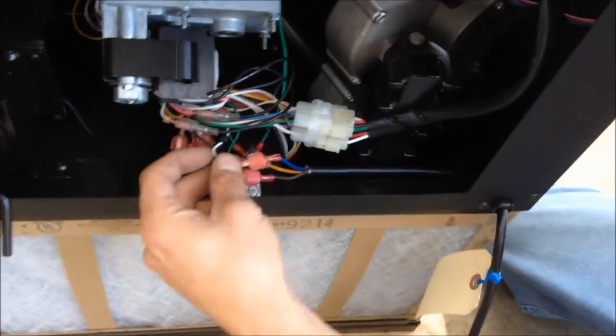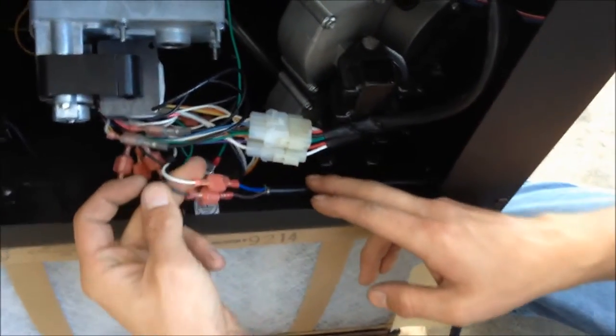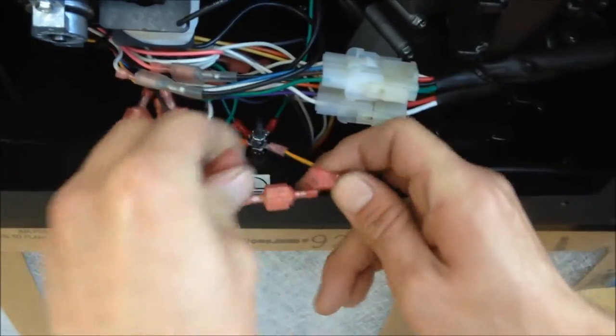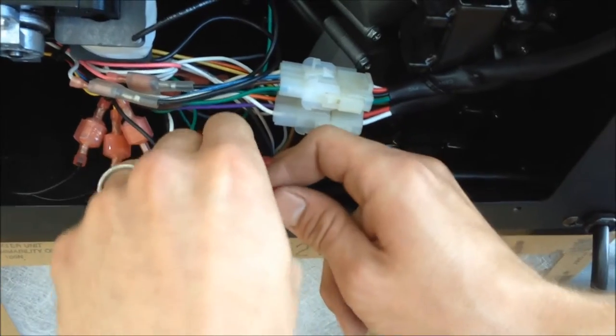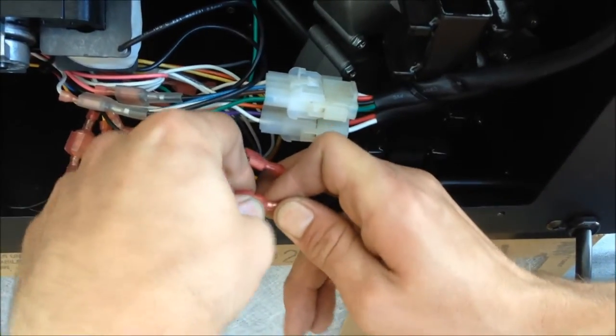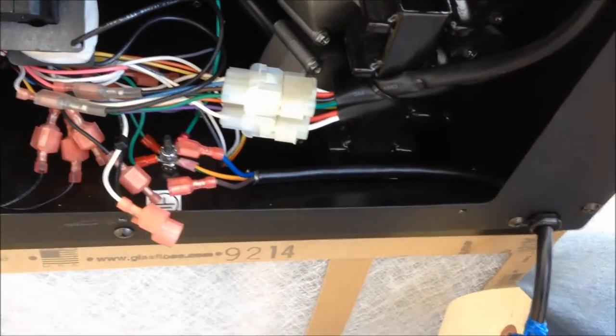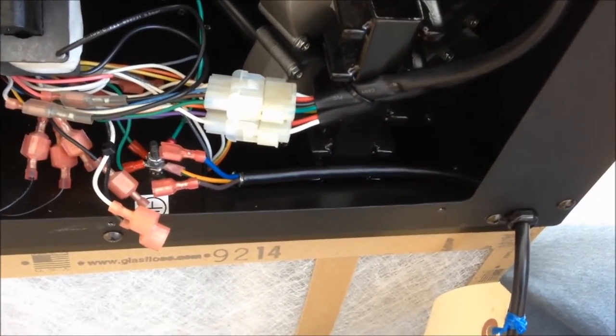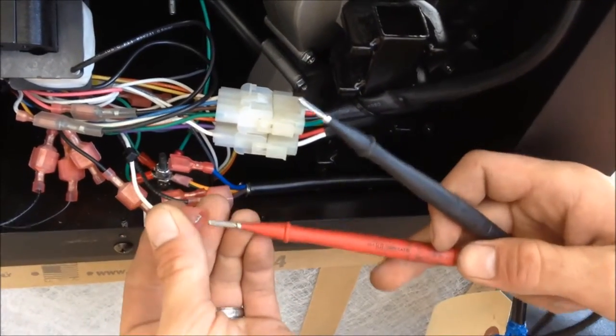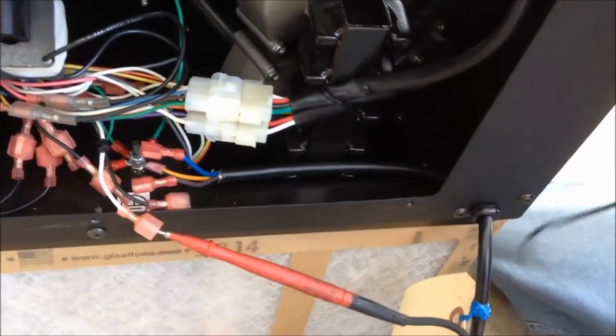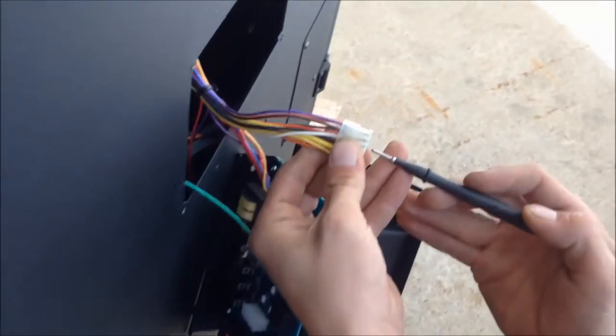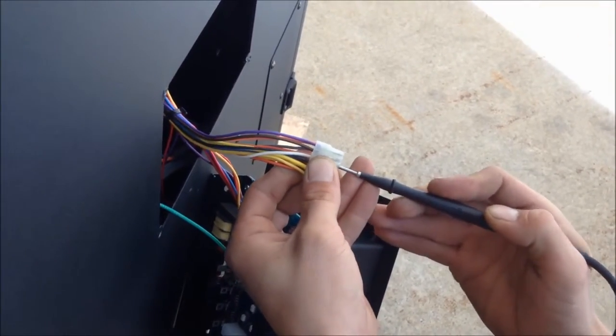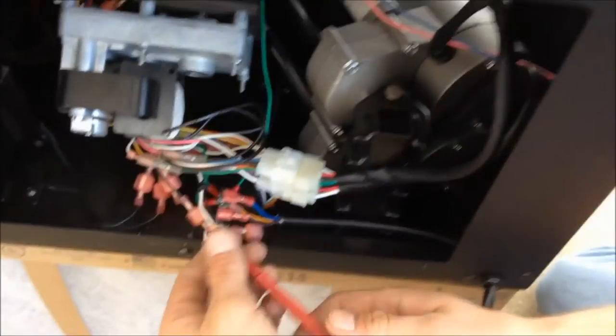So now what we're going to do is go back to the back of the furnace. And here is where our power is connected. I'm going to disconnect these, the white and the black to the blue and the brown, or in some cases also a white to a white and a black to a black. Again, using continuity checks, we're going to check our white to our white. And we do have continuity, so there is no break in the line.